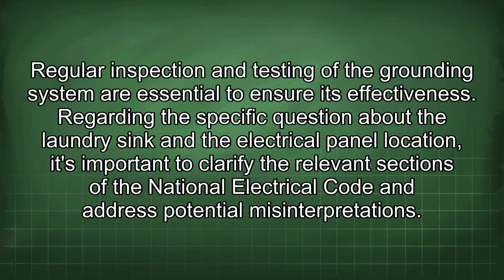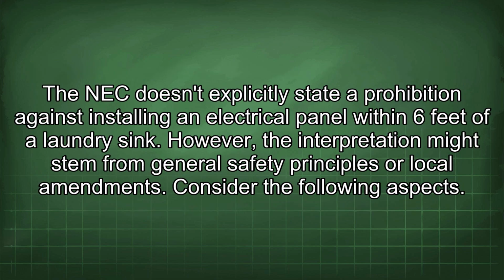Regarding the specific question about the laundry sink and the electrical panel location, it's important to clarify the relevant sections of the National Electrical Code and address potential misinterpretations. The NEC doesn't explicitly state a prohibition against installing an electrical panel within 6 feet of a laundry sink. However, the interpretation might stem from general safety principles or local amendments.